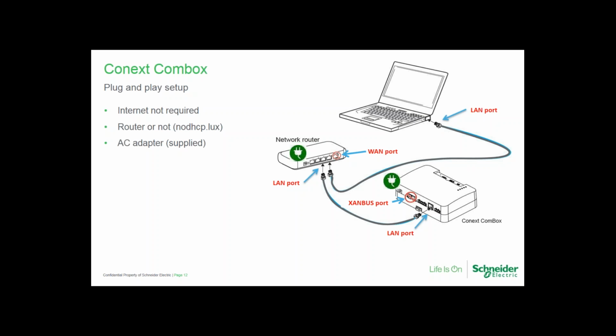But yeah, absolutely, if you're off-grid, or if the router happens to be powered from the output side of the inverter and you need to upgrade the power producing device, which is the inverter providing AC to that router, then make sure you're bypassing the XW system if you're on grid, or make sure you're bypassing the XW system with your generator if you're off grid. Great question.